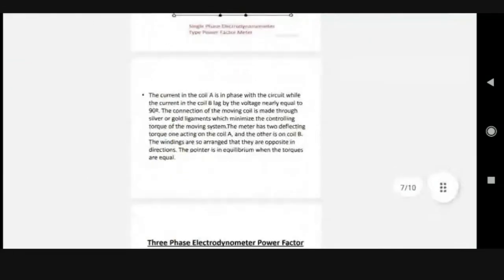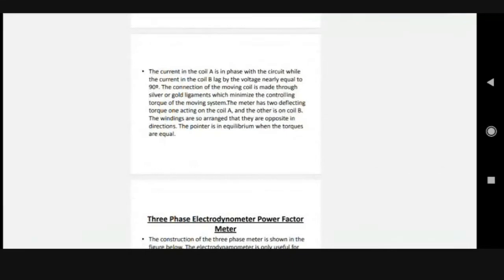The current in coil A is in phase, while the current in coil B lags the voltage by nearly 90 degrees. The connection of the moving coil is made through silver or gold ligaments, which minimize the controlling torque of the moving system. The meter has two deflecting torques, one acting on coil A and the other on coil B. The windings are arranged so that they are opposite in direction. The pointer is in equilibrium when the torques are equal.